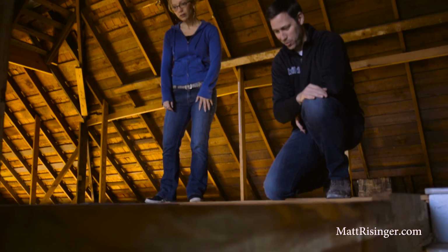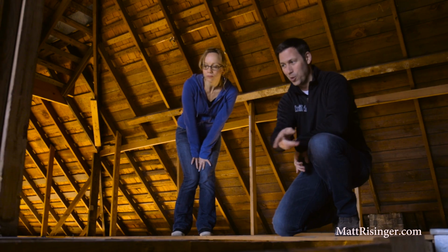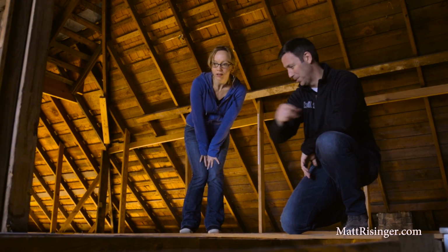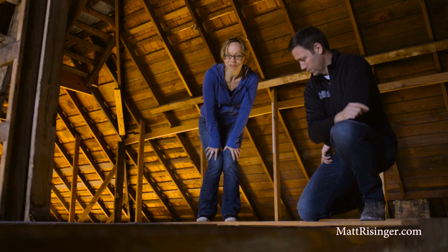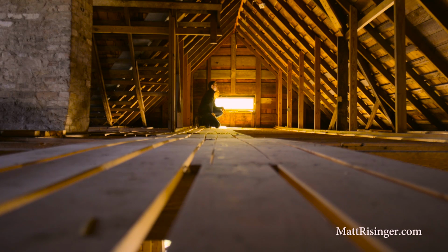And even all those things like how thick's our insulation? Do we have exterior insulation? What's our roof type? What's the U factor on our windows and the solar heat gain coefficient? These guys get super detailed, even down to the point of measuring the square footage of the glass and which way it's facing. So that load calc, or the Manual J as it's often referred to, is super detailed and very precise from your company. What's next when that load calc's done?